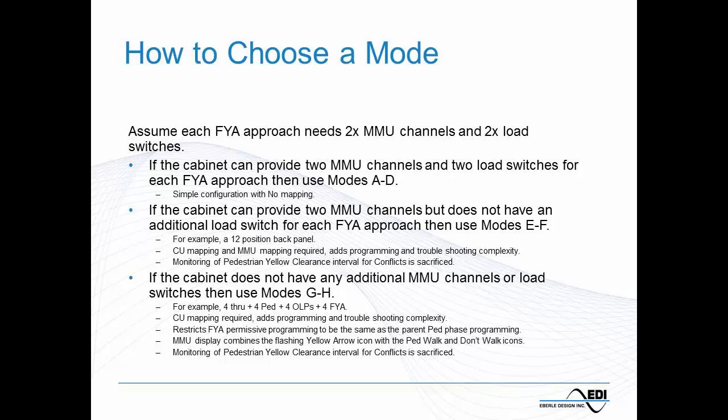So the first 4 modes, before we get into the detail, I'll give you the overview. The first 4 modes are what I call the simple configuration. There's no I/O mapping required in the controller. What you see on the back panel with the load switches is what you'll see on the MMU.